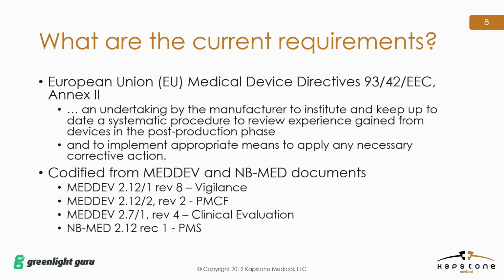The directive, in Annex 2, which is your full quality assurance system, requires a manufacturer to institute and maintain an up-to-date systematic procedure to review experience gained from devices in the post-production phase and implement the appropriate means to apply any necessary corrective action. Also, the various MedDev documents and requirements within the harmonized standards provide additional guidance on how this was intended to be achieved and demonstrated. And here's just an overview of these MedDev documents, these are the current revisions and what is currently available. So much of the content of these MedDev documents has now been codified into the new medical device regulations. A note on these MedDev documents: it is anticipated that the guidelines will be followed unless there is national legislation that differs. So if your organization has been following these documents, your adoption of the new regulations is going to be somewhat simpler.